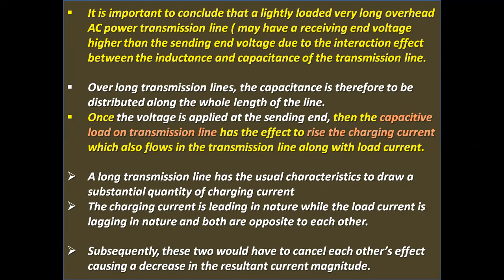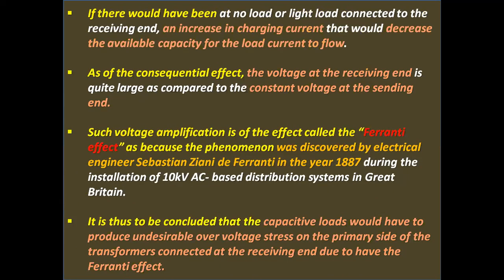A long transmission line has the usual characteristic of drawing a substantial quantity of charging current. The charging current is leading in nature, while the load is lagging in nature, and both are opposite to each other. Subsequently, these two cancel each other's effect, causing a decrease in the resultant current magnitude. If there is no load or light load connected to the receiving end, an increase in charging current would decrease the available capacity for the load current to flow.